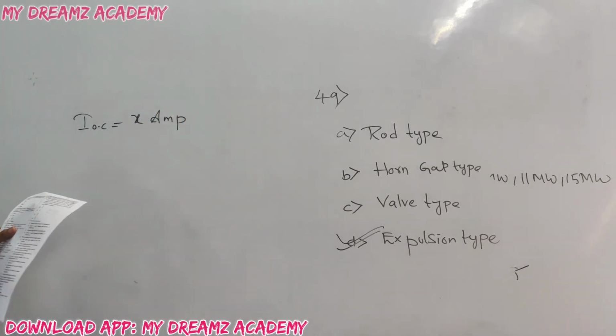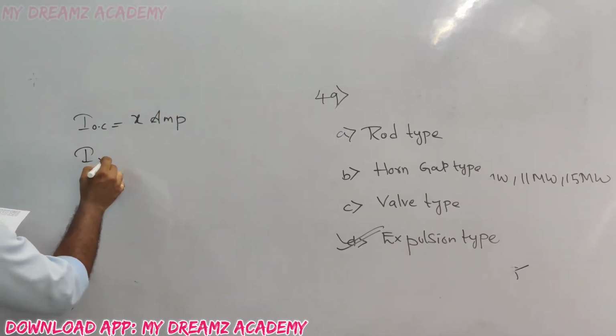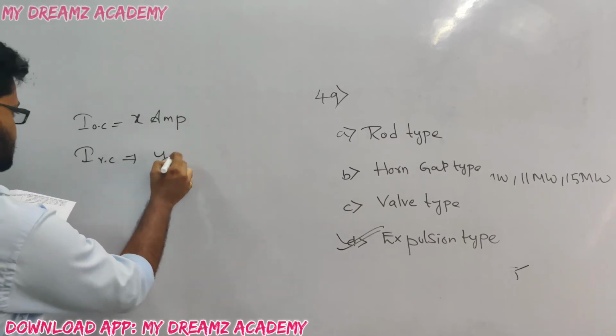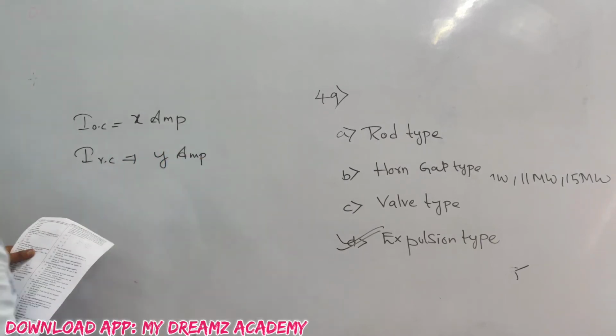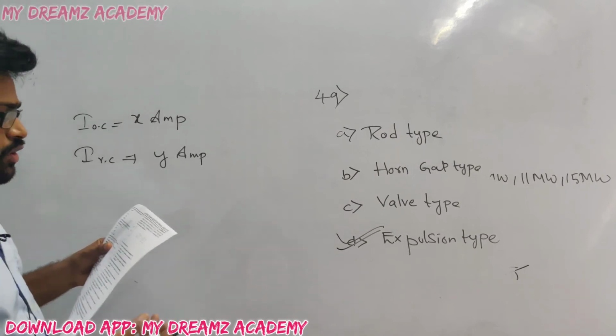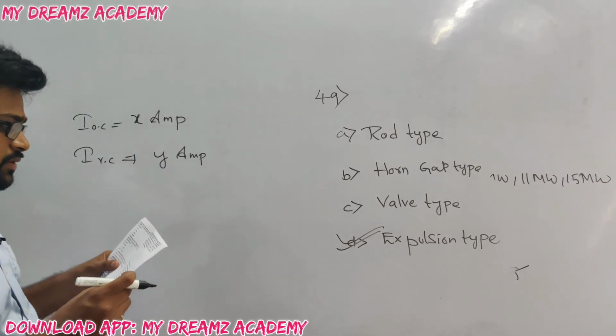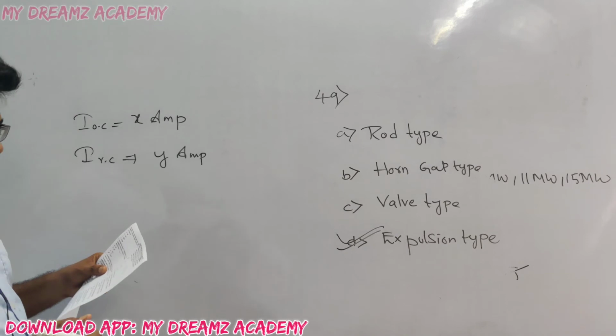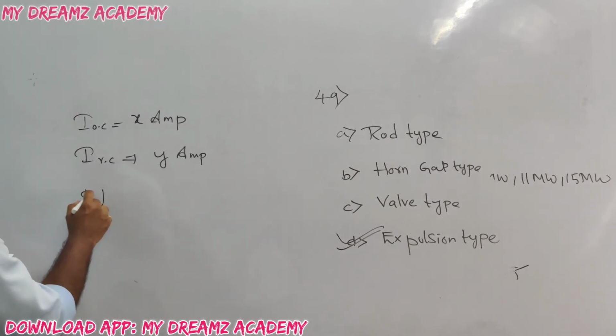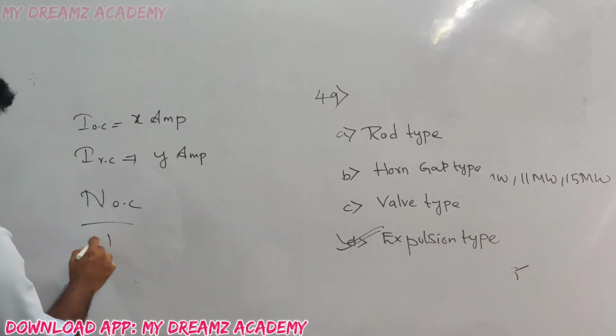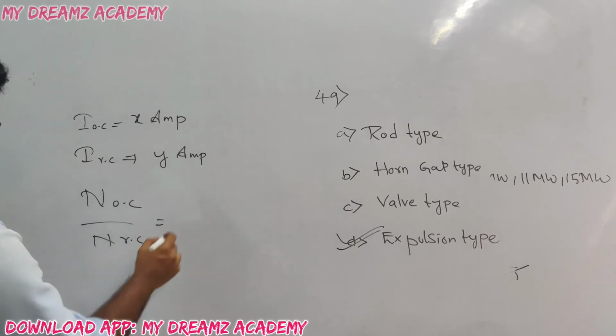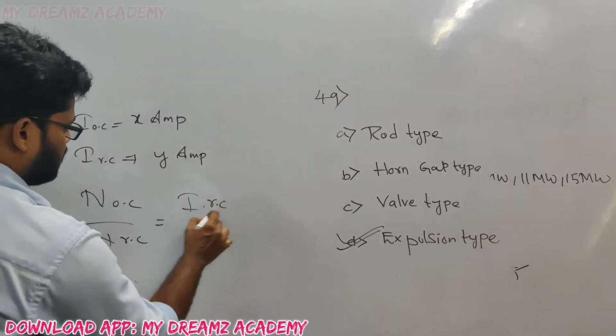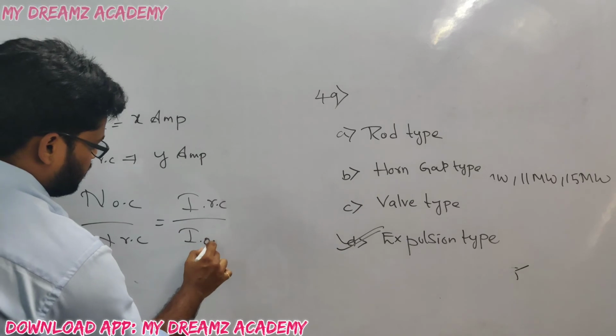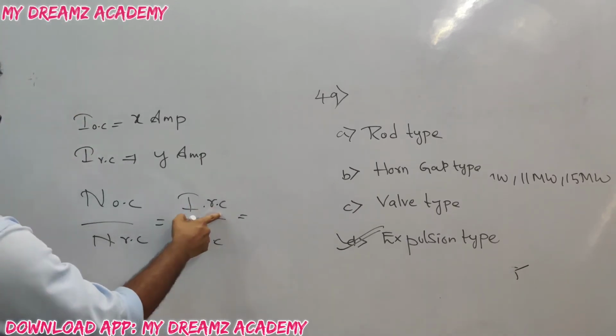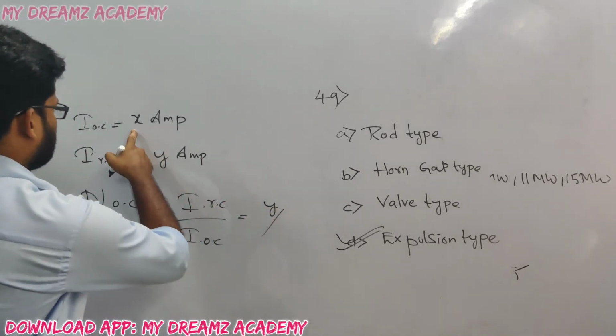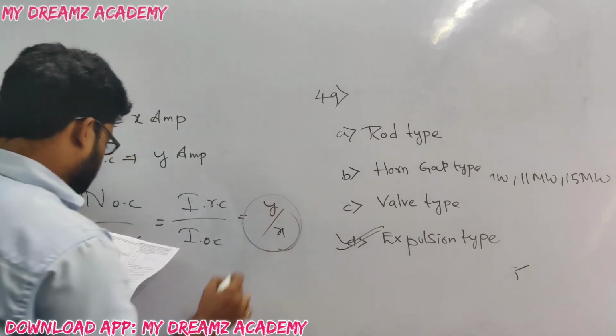Next, the average current in the restraining coil is Y ampere. Now the ratio of number of turns of the operating coil and the restraining coil: N operating coil divided by N restraining coil equals I restraining coil current divided by I operating coil current. So it gives restraining coil as Y and operating one as X. So the answer is Y by X.